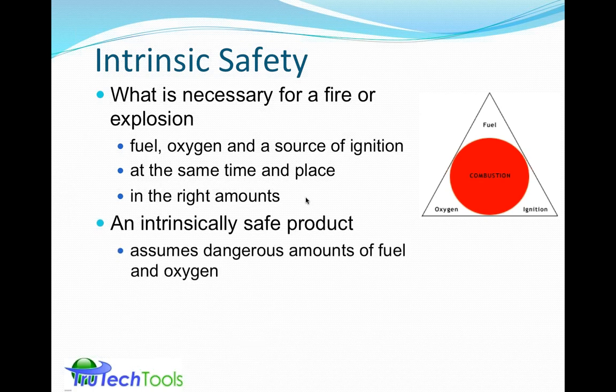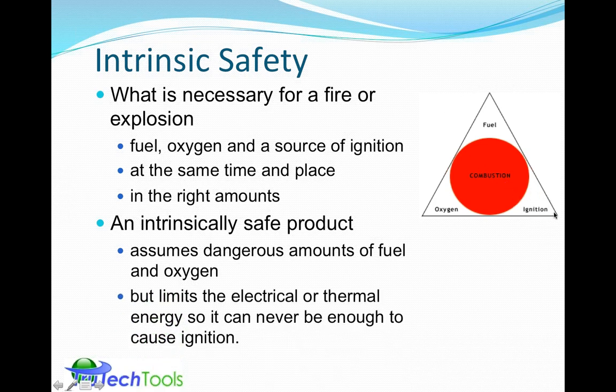An intrinsically safe product assumes that there are dangerous amounts of fuel and oxygen. It'll assume that this part of the triangle is in the danger zone, that you're in an area where you've mixed. And even though it's not exposed to it all the time, it assumes that it's going to be exposed to something that's in a dangerous combination of fuel and oxygen. And therefore, it will limit the ignition energy, the amount of thermal or electrical energy that the product itself produces, so it can never ignite a potentially hazardous atmosphere. So the product controls the ignition side of this because it can't control the real world, the fuel and oxygen side of it. So that's how an intrinsically safe product works.